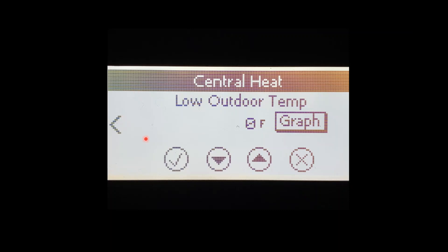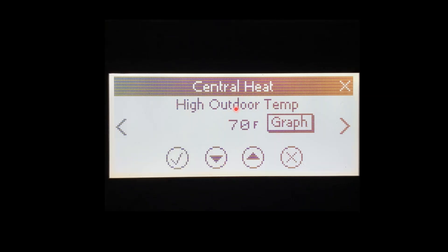With it enabled we're going to set the curve. Out of the box our low outdoor temperature is going to be zero degrees — so when it's zero outside the boiler is going to give 180 degree water out to the system. Factory settings are going to be: 0° outside / 180° boiler water, and 70° outside / 130° boiler water. 70 degrees is our factory setting for our high outdoor temperature, and at that point 130 degree boiler water is going to be going out.